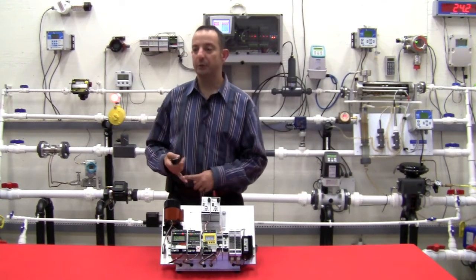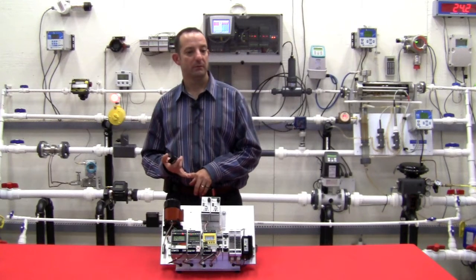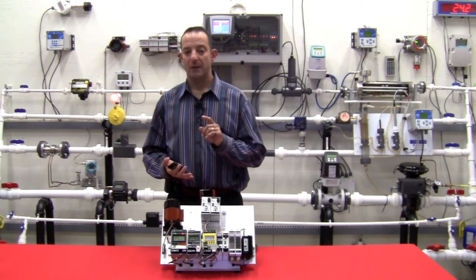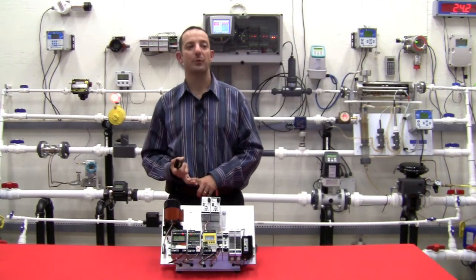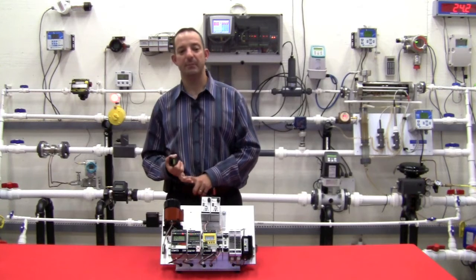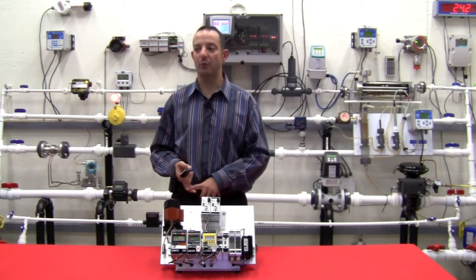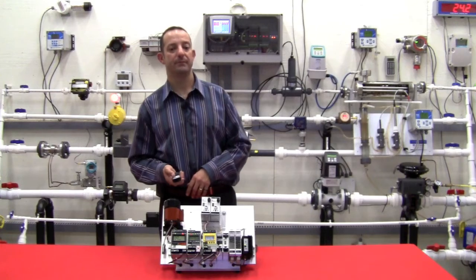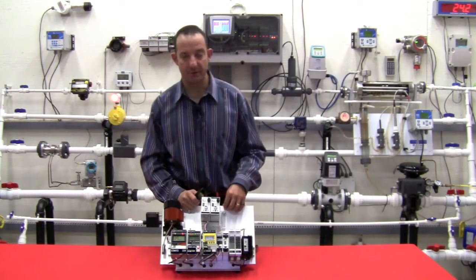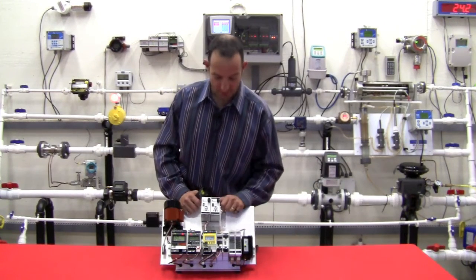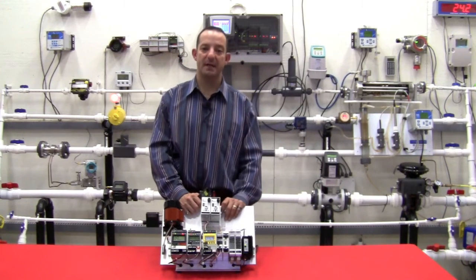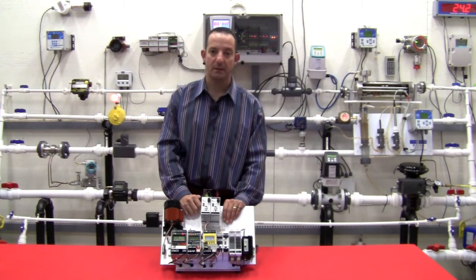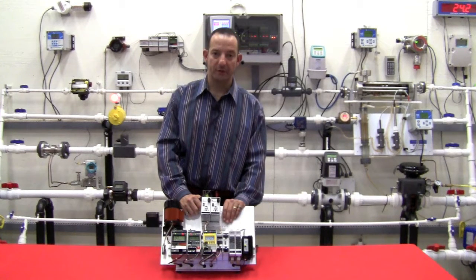You can choose between loop power and line power, and all of our temperature transmitters have that same minus 40 to plus 185 degree temperature specification, again giving you more latitude in where you can put these things. Our most popular temperature transmitter is the TRY here in the demo case. It's 1 inch wide and mounts on a DIN rail. And it can accept any thermocouple, any RTD, a millivolt signal, or a straight resistance signal.